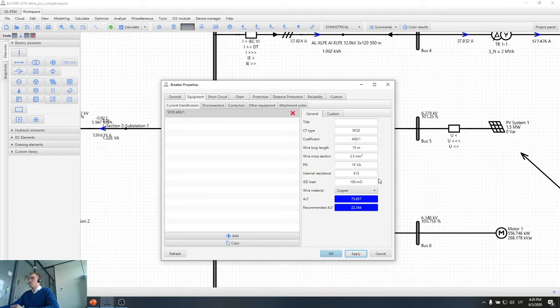And when I have these parameters provided, software automatically calculates what is the recommended accuracy limiting factor for the transformer, and in this case I see it's 22.3. So basically I will have to select a transformer with accuracy limiting factor bigger than 22, and it can be like 30. I can enter 30 here. Or if I want a transformer with a smaller accuracy limiting factor, I have to increase the current rating of the transformer. So if I increase transformer to 500/1, I can see that accuracy limiting factor 17 is enough. So I can select transformer with accuracy limiting factor of 20.